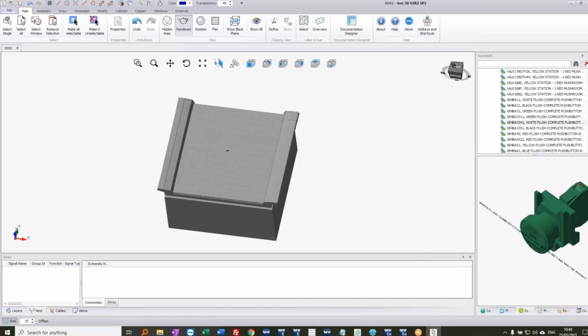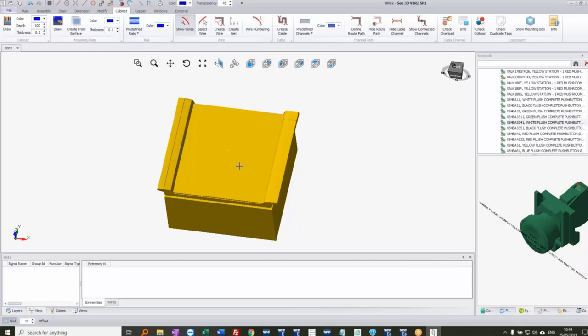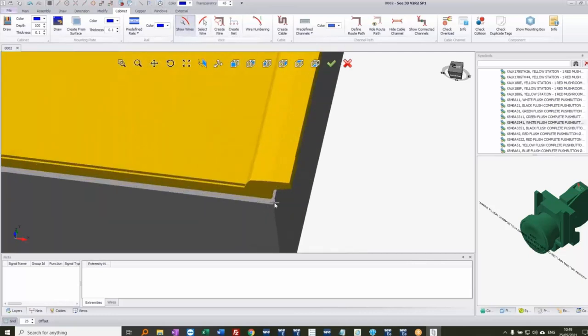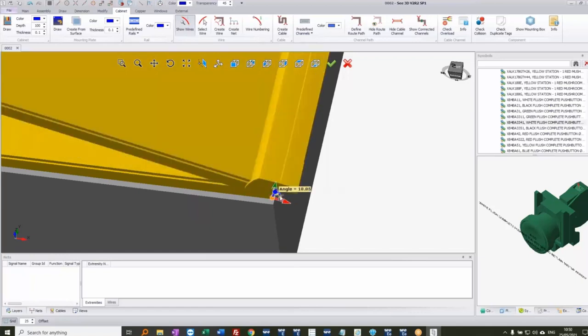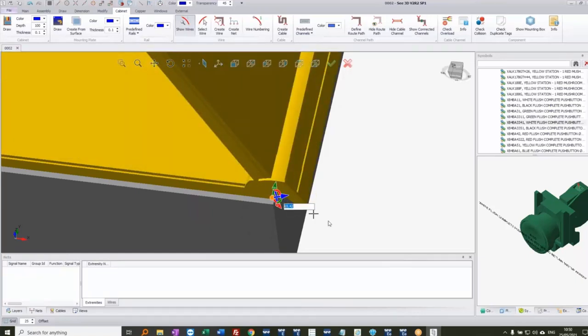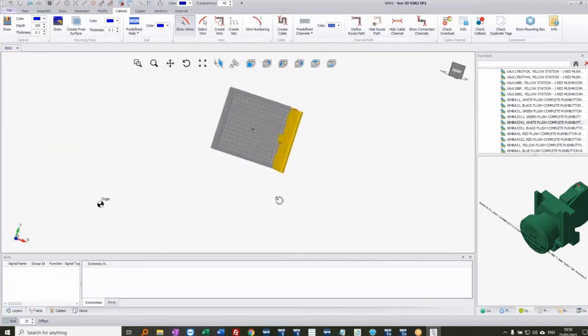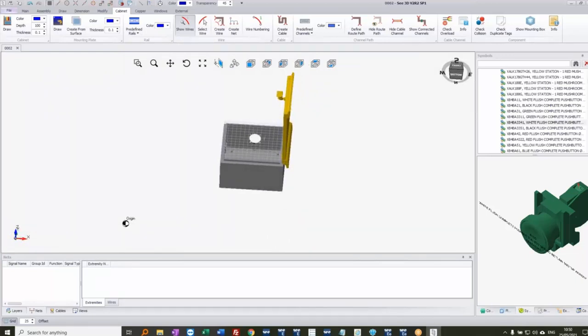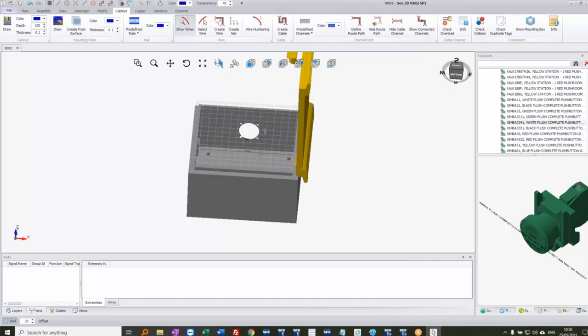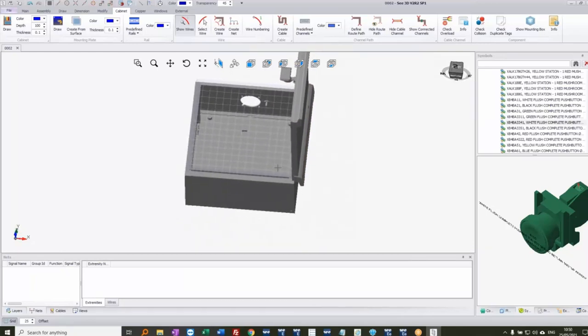I'll hit Delete to remove the placed push button. I can now start adding DIN rail and mounting components. I can also select just the door, use the modify command, tap R for reference, choose a corner, hit the spacebar to specify 90 degrees, and open the door to check for collisions with anything mounted on it. A bottom view lets me verify clearances as I design. There's lots of flexibility — quite intuitive.